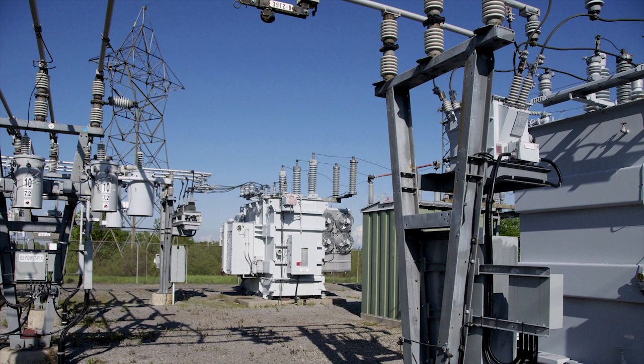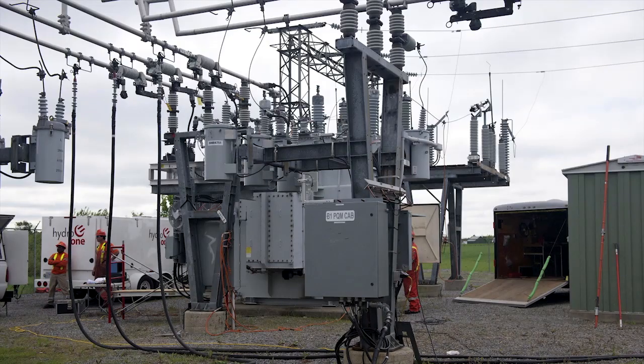When the MUS is installed at a DS, it will often bypass the existing station metering. If it does, an alternative method of metering is required while the MUS is in service in order to prevent loss of revenue and remain compliant with the IESO.